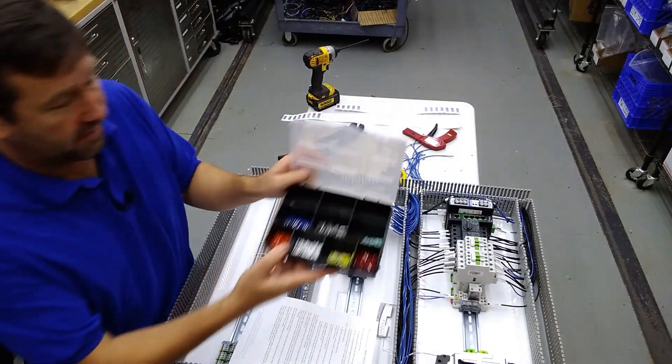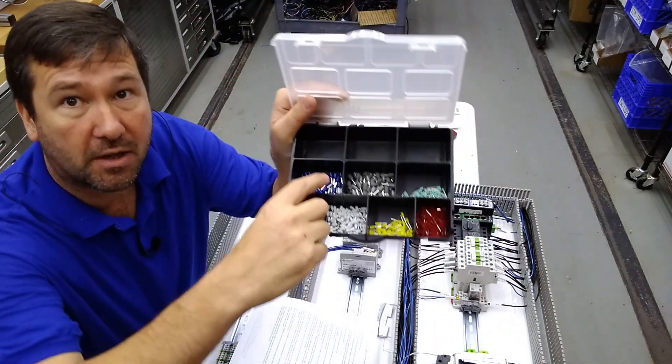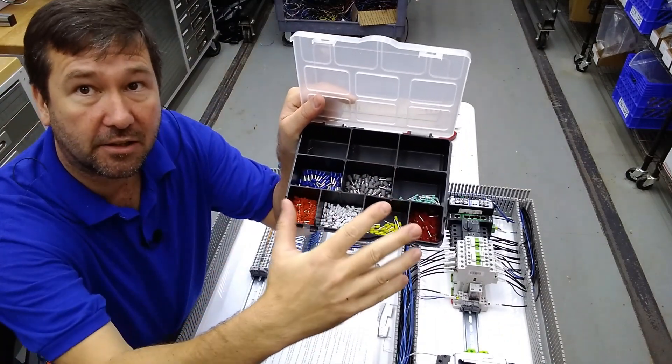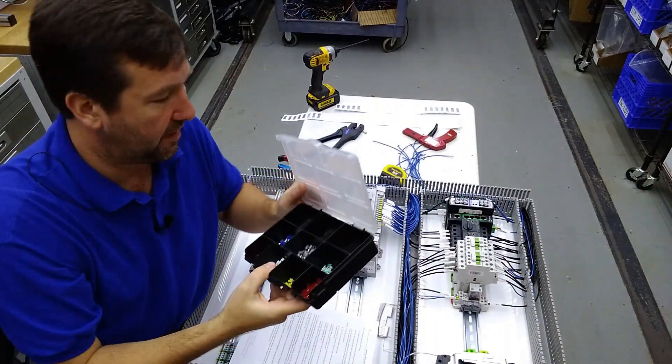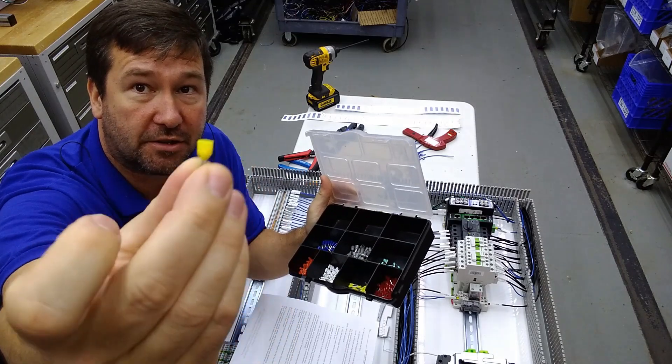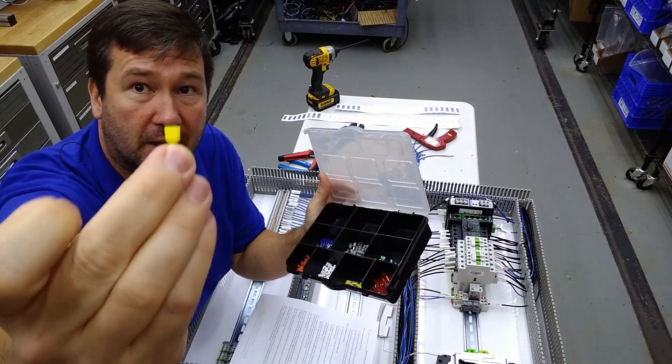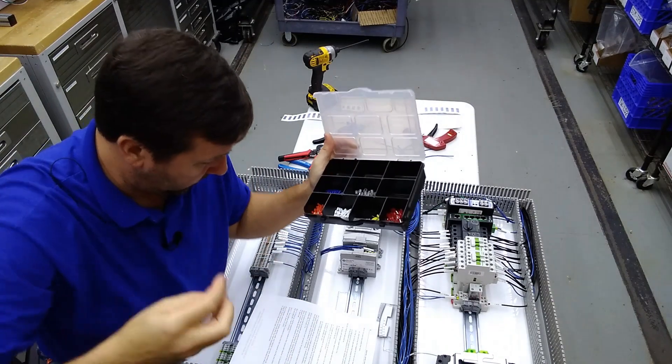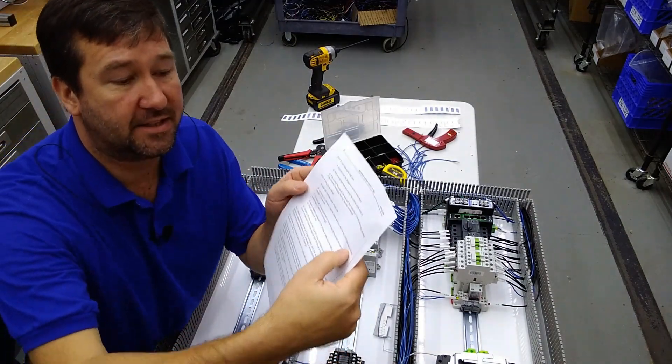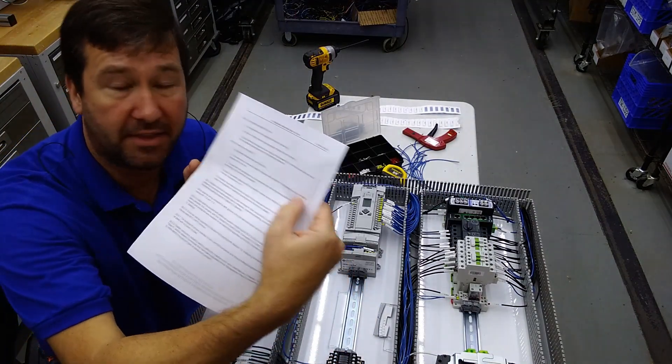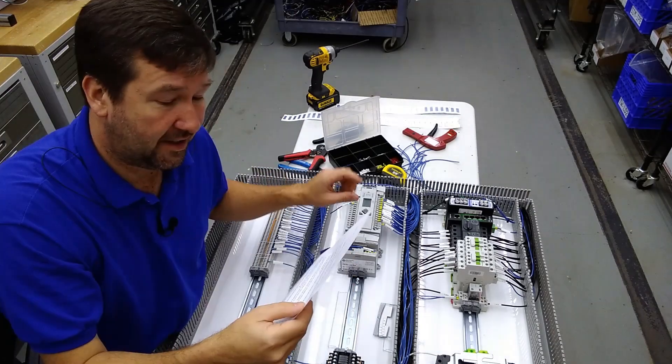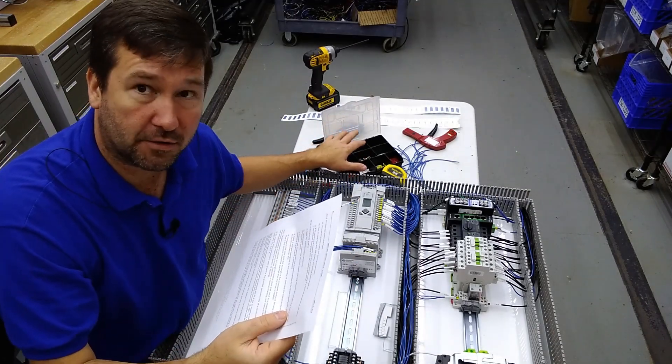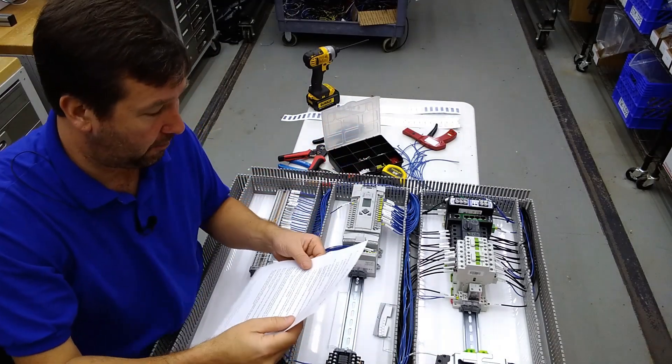One, the size - they are all color coded and each color typically is for a certain size wire. I'd always heard that you couldn't use these dual ferrules where you can stick two wires into one. But right there under B it does show 'size of wire' with an S in parentheses. So that tells me that these dual wire ferrules are okay for a UL panel.